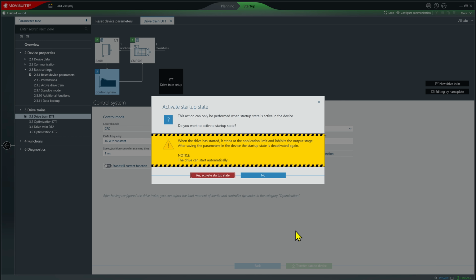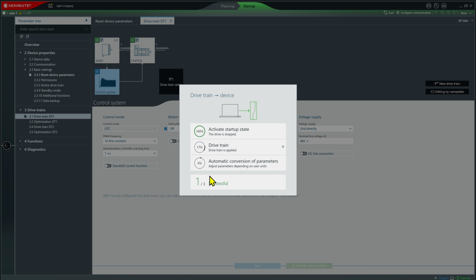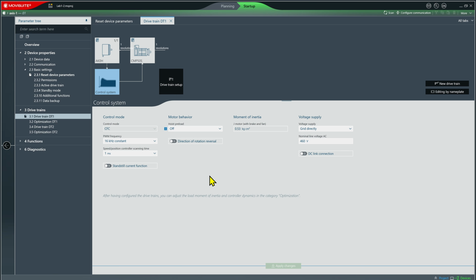And I get a warning here. Do I want to go to a startup state? Beware the drive could move and so forth. Okay, I've inhibited my drive, so that won't happen. So I click Activate Startup, and it chugs away briefly, and there we go. We're all done. Now we've done our basic commissioning, but now we need to go and set a few limits to make sure everything's appropriate, and then we need to do some testing.